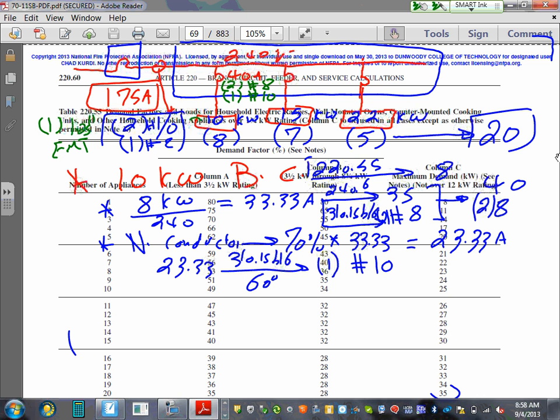Number 10. Oh, by the way, the code book tells you for branch circuits and feeders, you can't go less than number 10. So if I came up with less than number 10 for the neutral, I can't go less than number 10. I have to use at least number 10 for the neutral. In our case, we came up with number 10 anyway, so we don't have to. Had I come up with a 12, they don't allow you to do the ranges. You have to go minimum neutral number 10. That's why when you get into the neutral cables, guys, you can find two conductors, the hots are big and the neutral smaller, slightly smaller, based on this calculation. Am I the only one who's excited today?